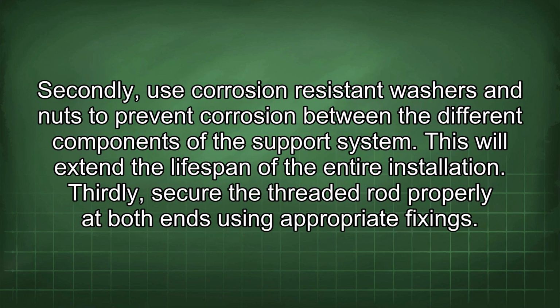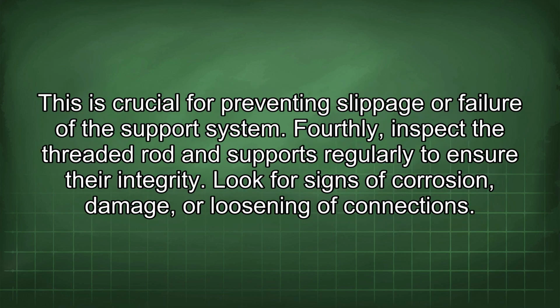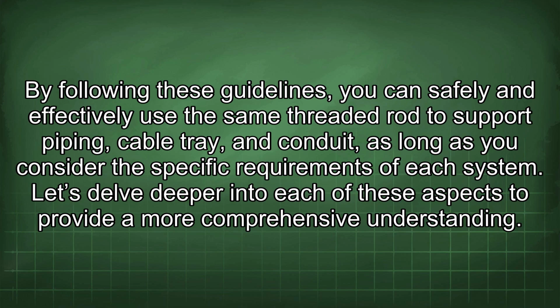Secondly, use corrosion-resistant washers and nuts to prevent corrosion between the different components of the support system. This will extend the lifespan of the entire installation. Thirdly, secure the threaded rod properly at both ends using appropriate fixings. This is crucial for preventing slippage or failure of the support system. Fourthly, inspect the threaded rod and supports regularly to ensure their integrity. Look for signs of corrosion, damage, or loosening of connections. By following these guidelines, you can safely and effectively use the same threaded rod to support piping, cable tray, and conduit, as long as you consider the specific requirements of each system.